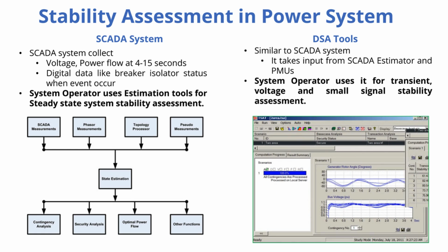What's its role? SCADA is the basic real-time monitoring system. It collects data like voltage, power flow, breaker status from across the grid, usually updating every, say, 4 to 15 seconds, as noted here. Operators use state estimators based on SCADA data, mainly to watch steady-state conditions, making sure things are within normal limits. It's generally too slow for fast dynamics. Okay, so SCADA gives the big picture snapshot.